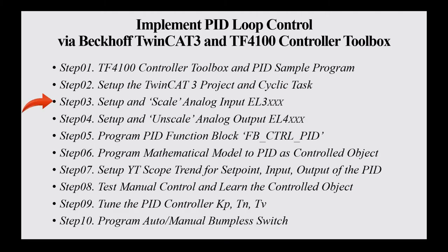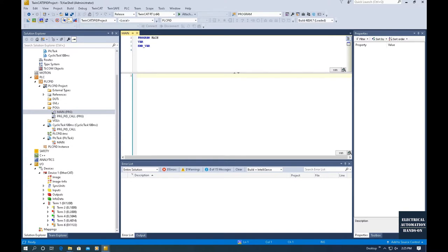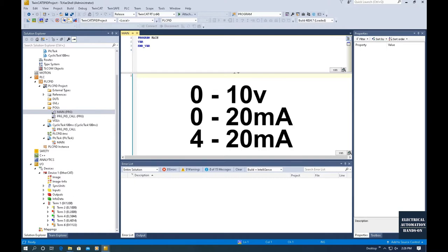Hello everyone. In this video we will discuss step 3: how to set up and scale the analog inputs. We will mainly introduce the hardware from the EL3000 Beckhoff analog input cards. We use different kinds of transmitters or sensors to get sensor signals as process feedback. The commonly used signals from sensors are basically 0-10V or 4-20mA, and in some cases 0-20mA — current or voltage signals. To receive those signals, we use analog cards.